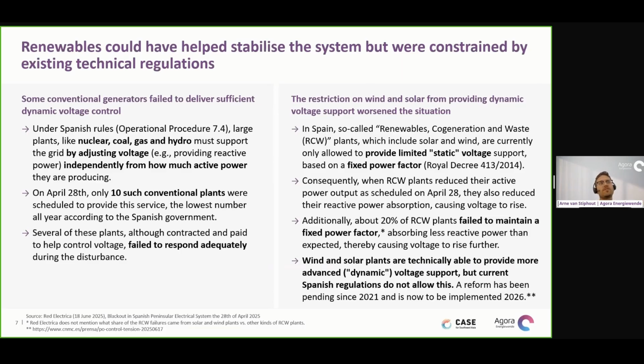So on the left first, thinking at the conventional generators, these were the ones, so we're looking here under Spanish rules, nuclear, coal, gas, and hydro, that have to support the grid by adjusting the voltage independently from how much active power they're producing, what we will call dynamic voltage control. On April 28, there were 10 of such conventional plants that were scheduled to provide this service, which the Spanish government itself pointed out was actually the lowest number all year. So there are some questions there.